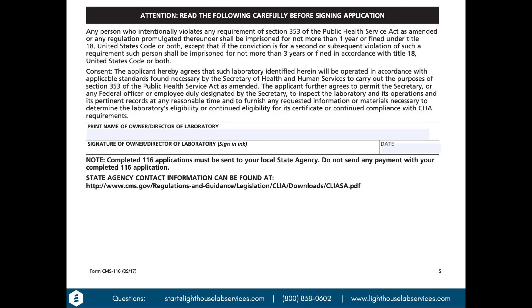When you send this in, you'll need to include your laboratory director's resume as well as a copy of their board certification. Do not send any payment with it at this time — they'll let you know what you owe once they process your application. You're not allowed to start diagnostic testing until you receive approval from the CLIA office. Processing typically takes 30 to 45 days depending on your local office. In most states, you are allowed to begin validation work ahead of approval — you can send the application in, get your equipment and supplies, and start validating. Those are not diagnostic tests on human samples.